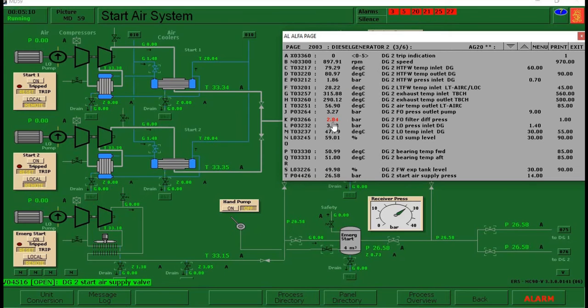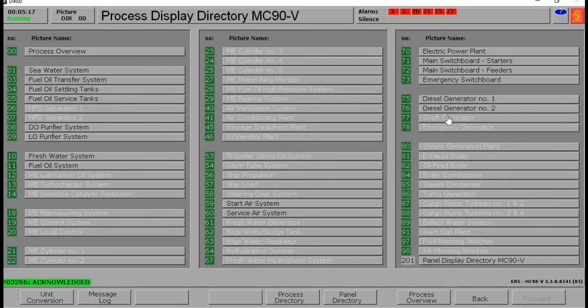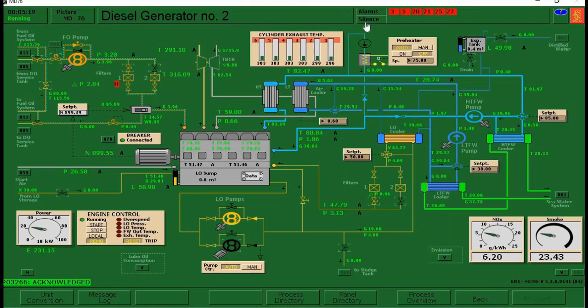Okay, so there is an alarm. So just acknowledge the alarm. Our diesel generator 2 filters. Okay, so there is a high differential pressure here. You can see our pressure rising here. So we need to change over the valves. So we open this 2 and close this 1. Okay, so after that our system should operate normally.